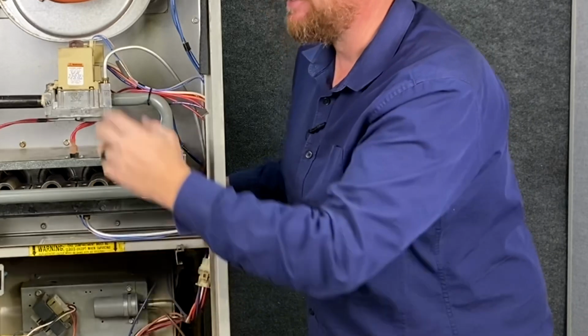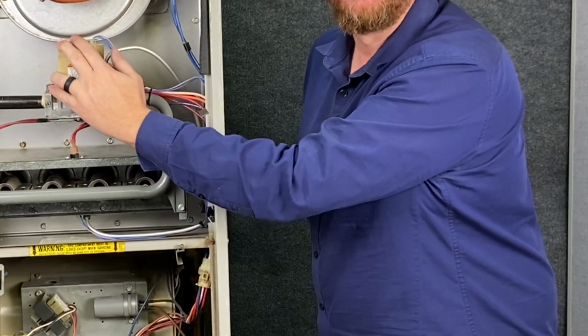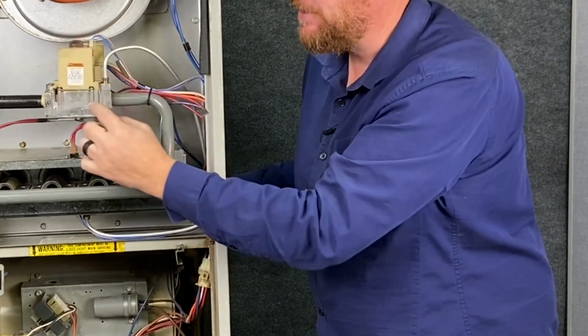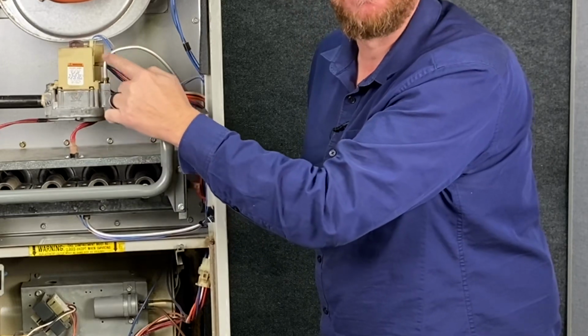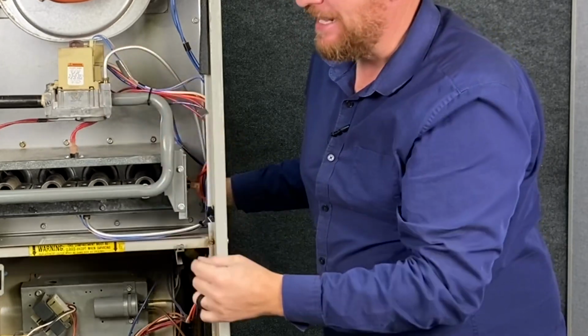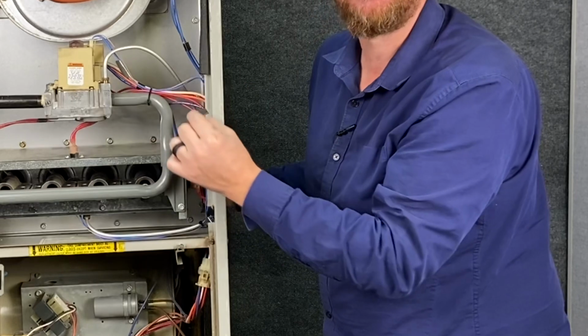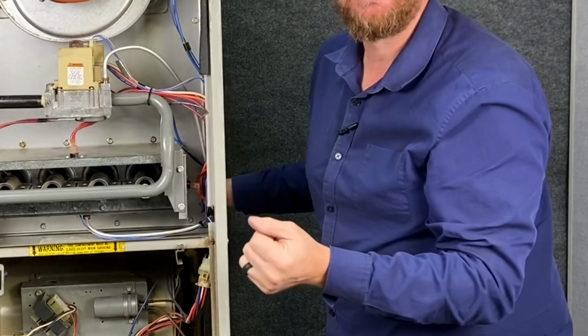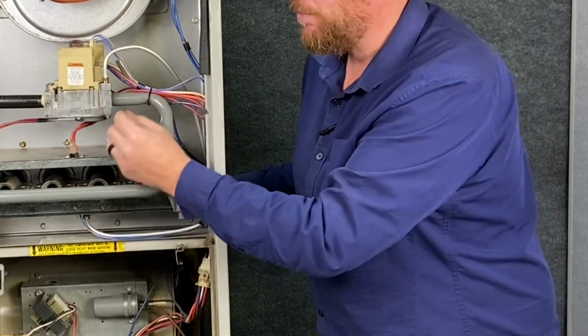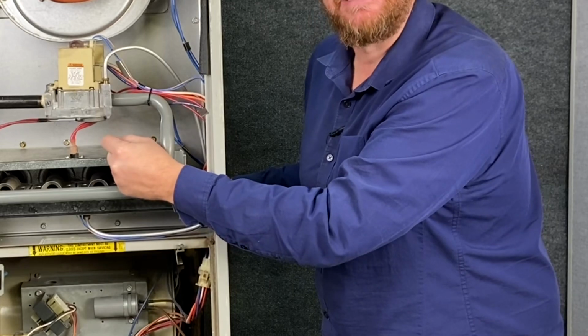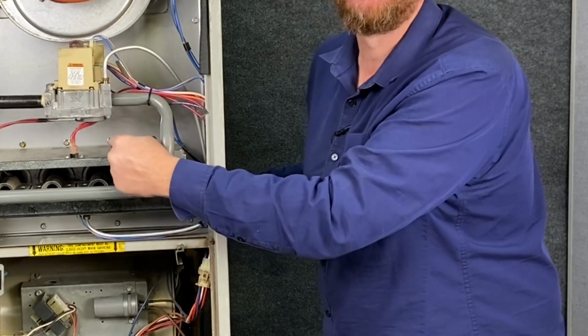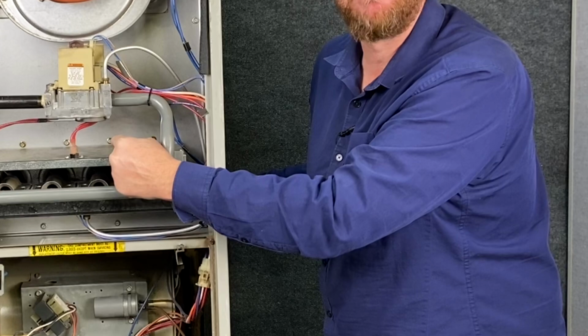Then the IFC sends a signal to the combination gas valve. The combination gas valve then opens this little bitty pilot solenoid and allows gas to flow through the pilot tube. It also energizes a miniature hot surface igniter. And we're going to show that here shortly. We're going to take all this apart. That hot surface igniter ignites the pilot light. There's a miniature flame sensor back here that's going to prove a flame through flame rectification.